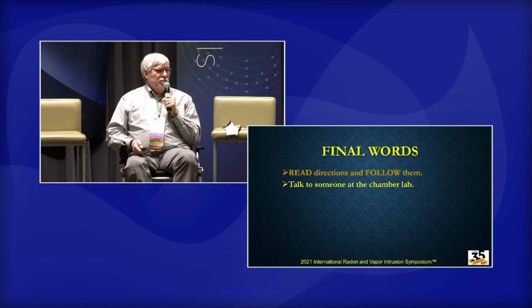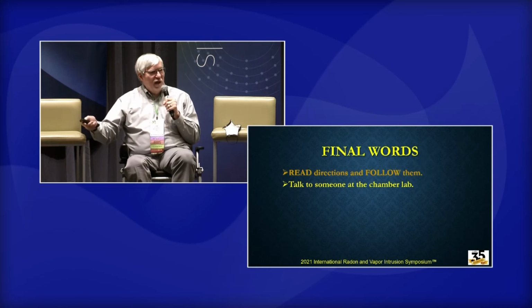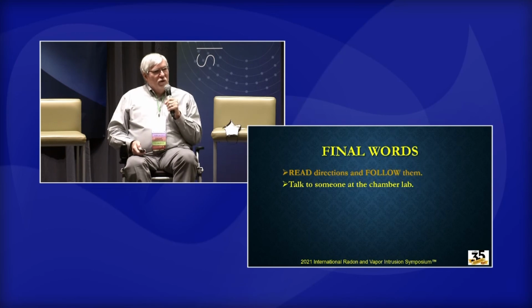In Kansas, I know they force you to talk to someone at the chamber. In our lab, we send you a work agreement, and if the work agreement says you ask for, let's say, a performance test on a monitor, and you get it back, and then you're calling us and you're saying, well, where's my calibration certificate? Well, you didn't ask for a calibration, and the work agreement didn't say anything about calibration. Oh, well, I assumed that you would do a calibration too. Well, don't assume anything, people.